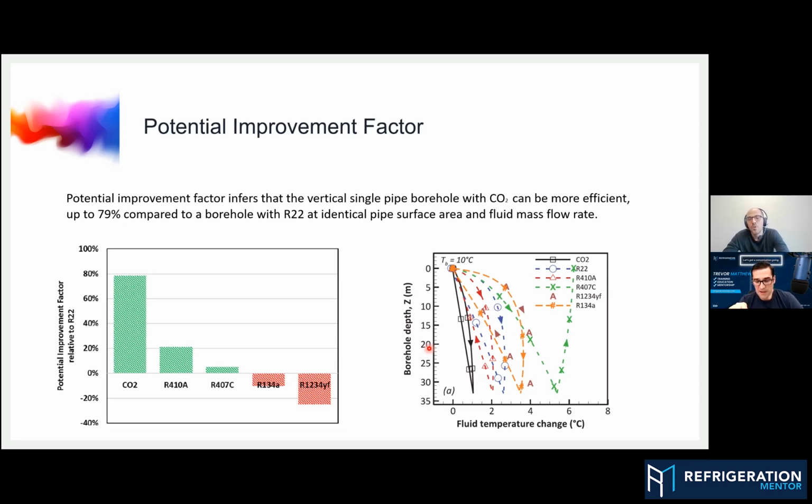Yeah, I looked up that number as well. So 100 kilopascals equals 1 bar. I should have known this right off the top of my head, which is 14.5 psi. Exactly. That's a big difference in a standard refrigerant if you got a 14.5 psi pressure drop versus CO2. That's huge. Yeah, for some refrigerants it's not acceptable. You cannot do that. But for CO2, the power consumption to compensate for that is pretty insignificant, and the temperature change is less than a degree. That's a good thing about CO2.